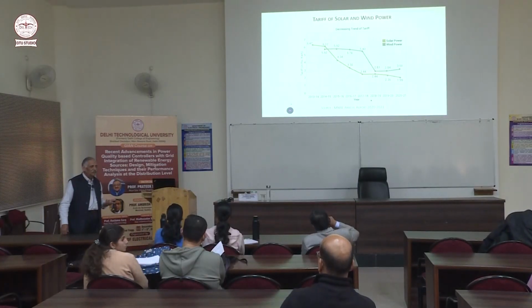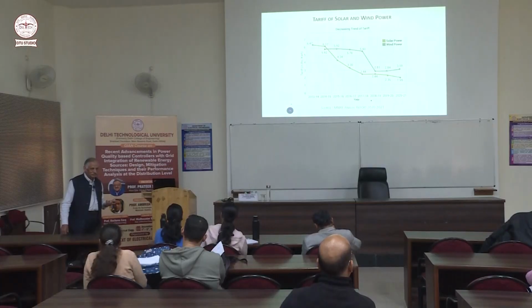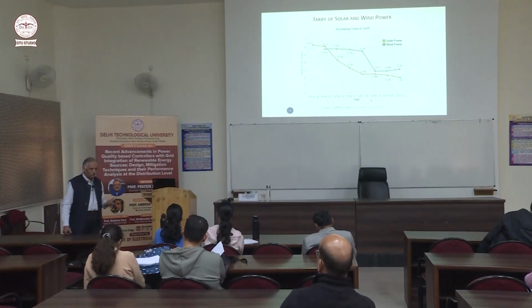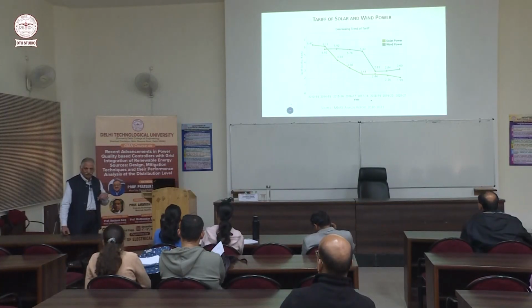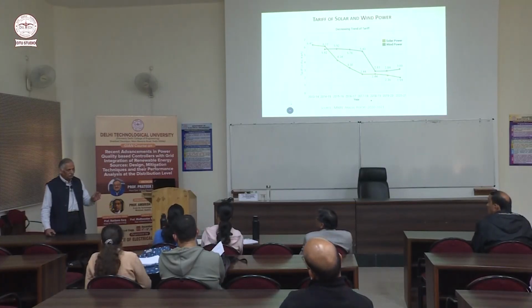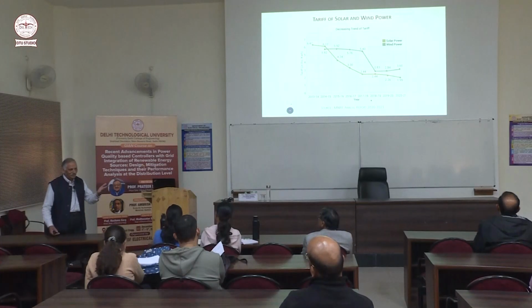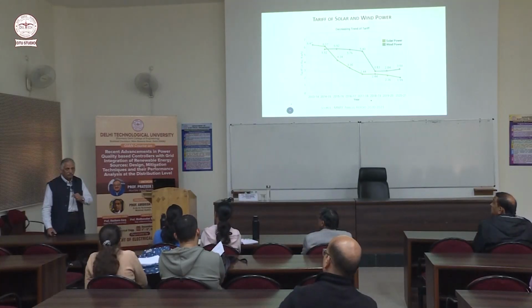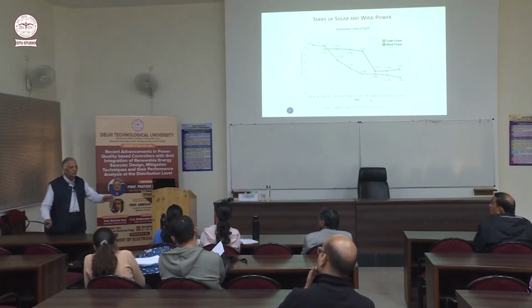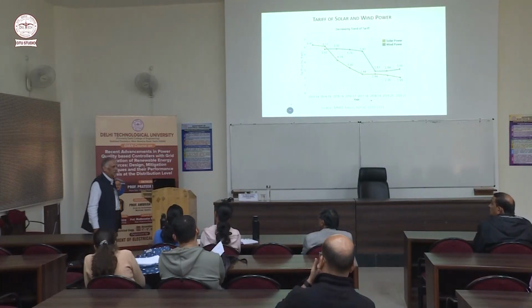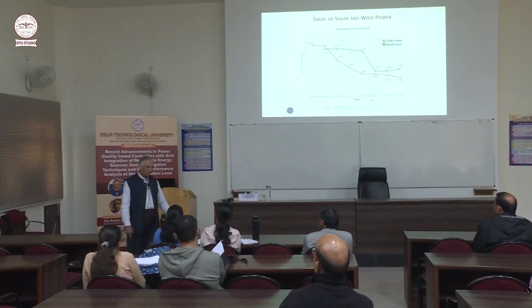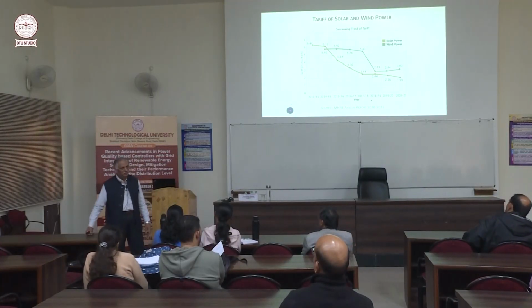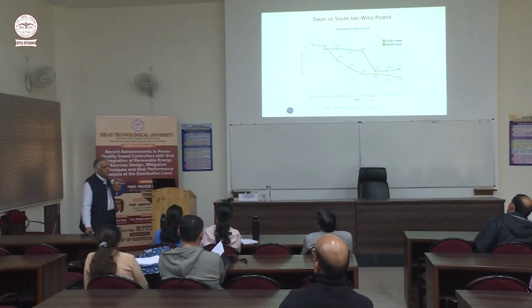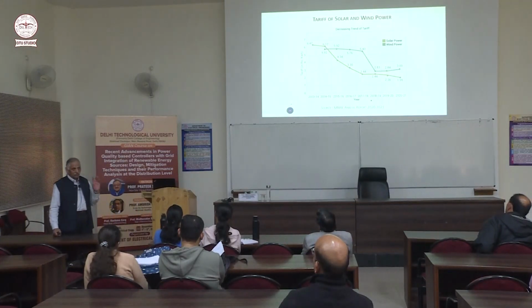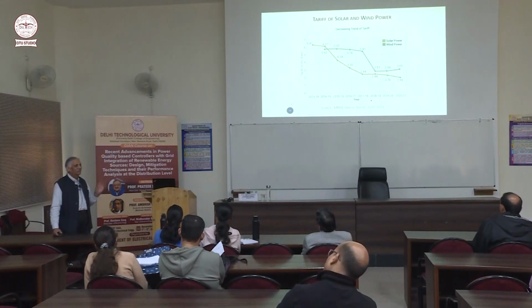This happens because a solar panel connected in series is virtually a current source. Voltage doesn't change much, but current changes across power generation, from zero to full. So if the current of one module reduces, it reduces the current for all 22 modules connected in that string, and they observed around 15 to 20% reduction in power generation.